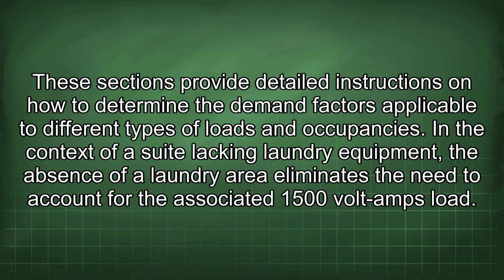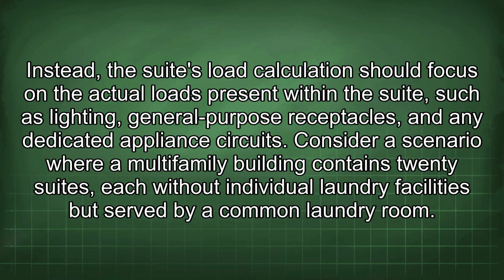These sections provide detailed instructions on how to determine the demand factors applicable to different types of loads and occupancies. In the context of a suite lacking laundry equipment, the absence of a laundry area eliminates the need to account for the associated 1500-volt amps load. Instead, the suite's load calculation should focus on the actual loads present within the suite, such as lighting, general-purpose receptacles, and any dedicated appliance circuits.